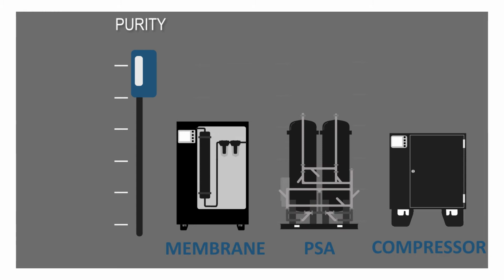Note here that nitrogen from bulk liquid always comes at high purity, and the gas purity you may be used to is likely to be higher than that you would actually need. Your generator supplier can advise on this matter. And at Holt we can help with industry references or a test plan to help you determine what purity you need.